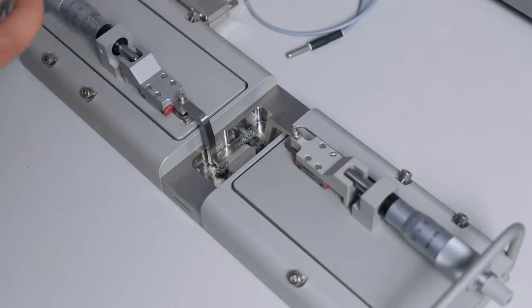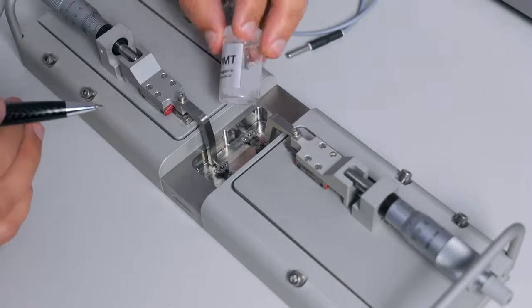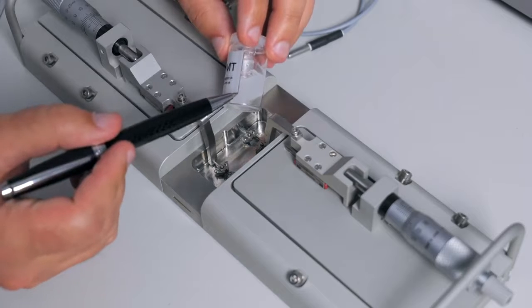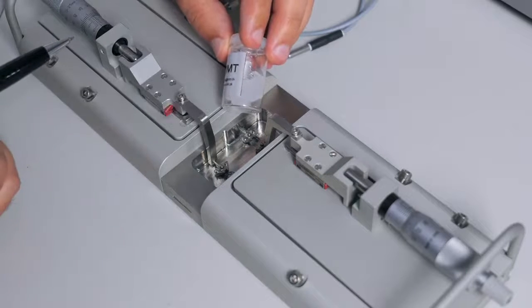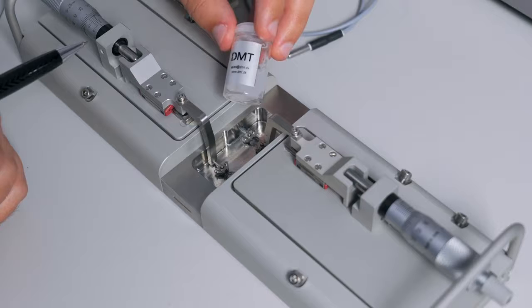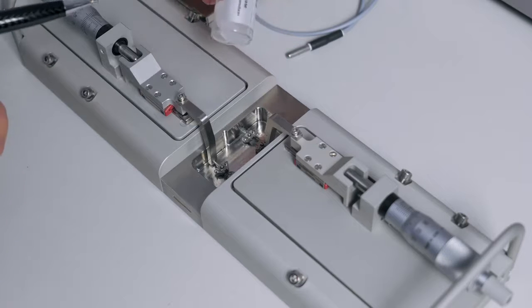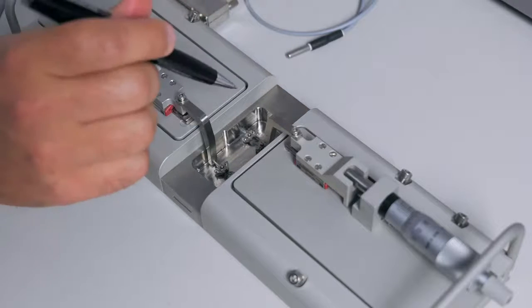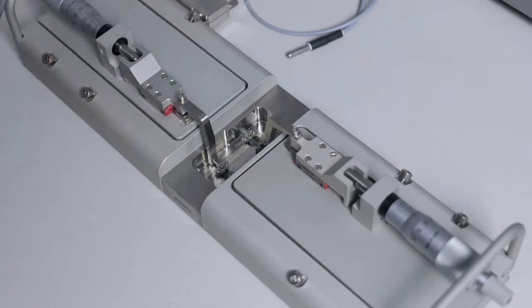The transducer is made up of electronics, so you need to make sure that it's completely protected from any liquid. Make sure that you use the clear silicone-based grease for this purpose. If you need to add more grease, you can use a pipette tip and just add more as necessary.